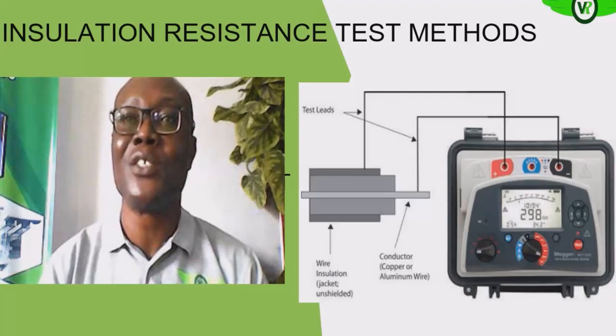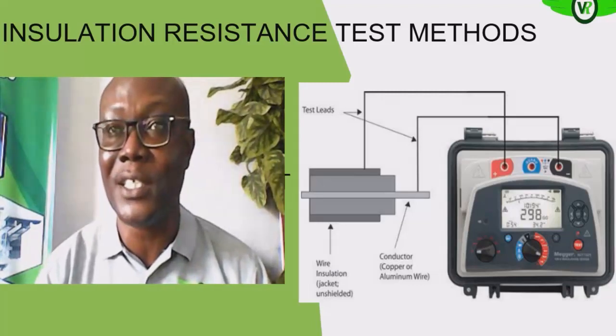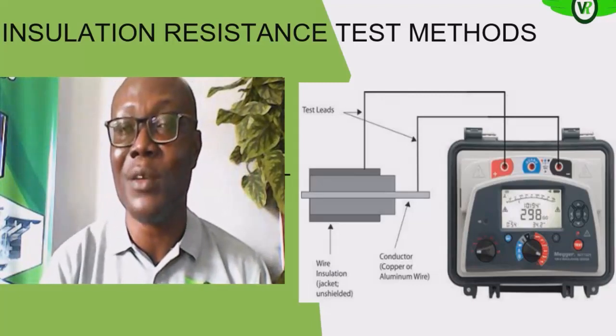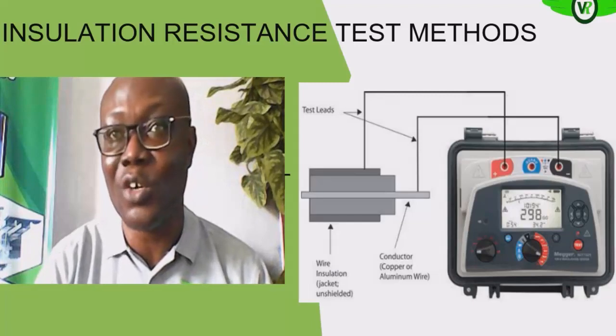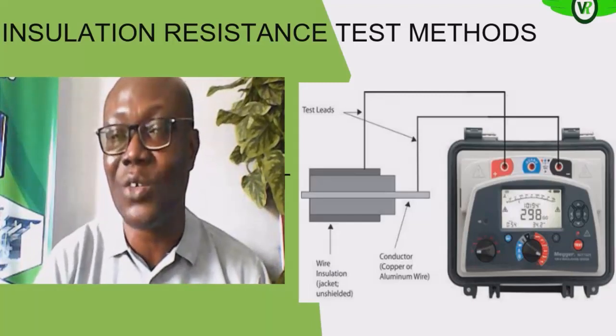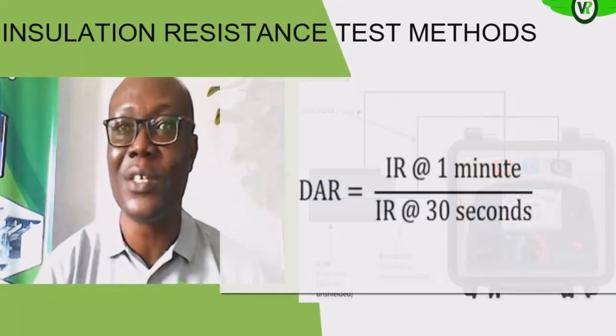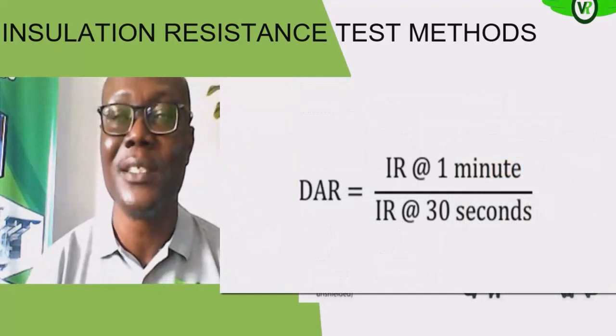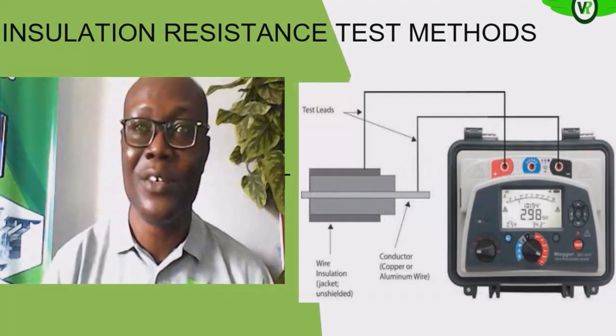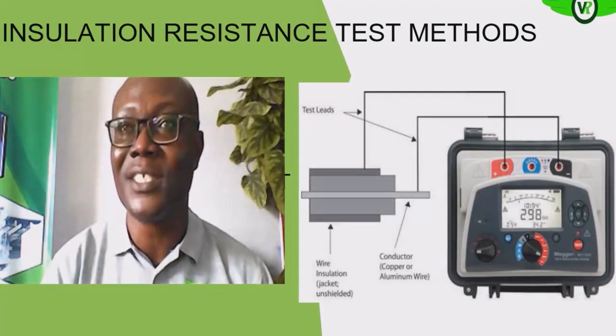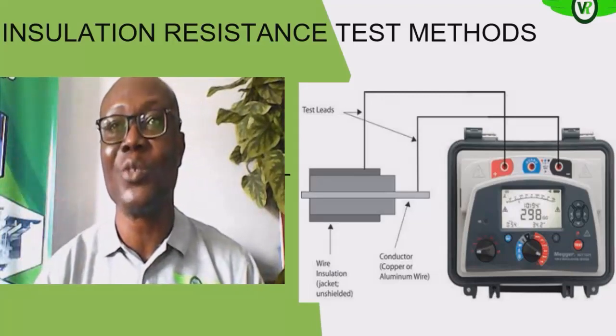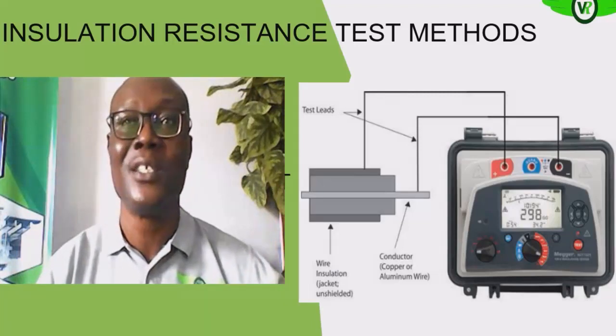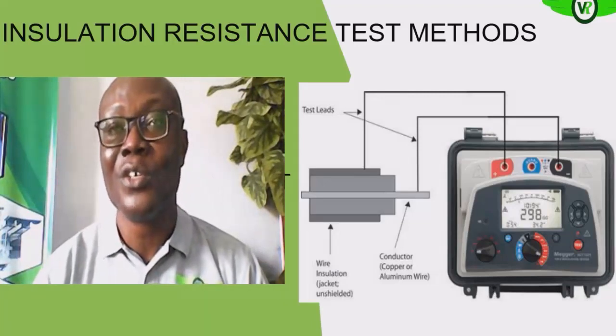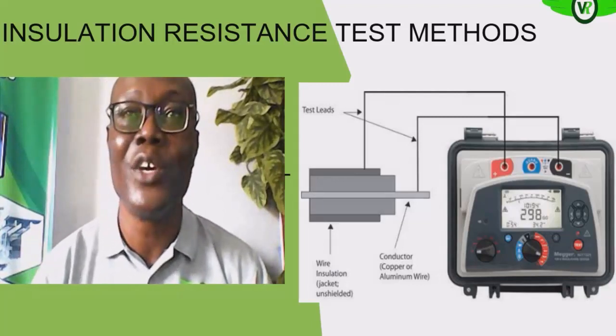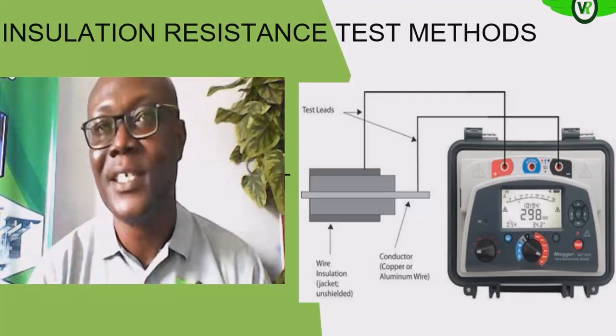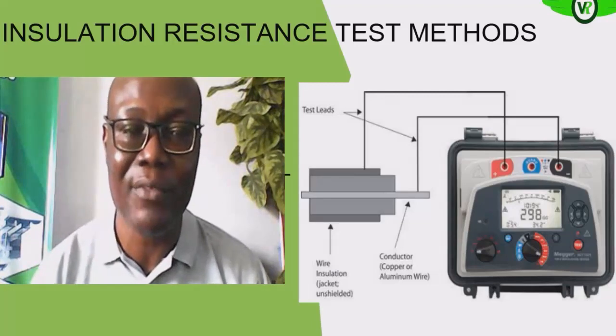Which means that as you are injecting the test voltage, you record the insulation resistance reading at 30 seconds or 20 seconds, then you record the insulation resistance reading at 60 seconds, and then you divide that of 60 seconds by that of 30 seconds. From what we described earlier, you will see that the insulation resistance reading at 60 seconds is supposed to be higher than the reading at 20 or 30 seconds. So the ratio should be more than 1 for a good insulation. The higher the better, but if it is less than 1, that is a sign that we have a problem.